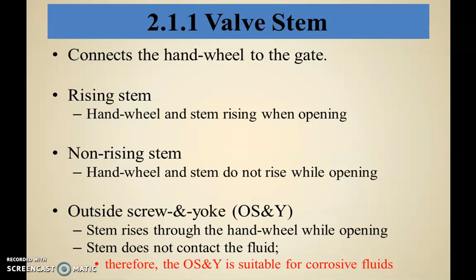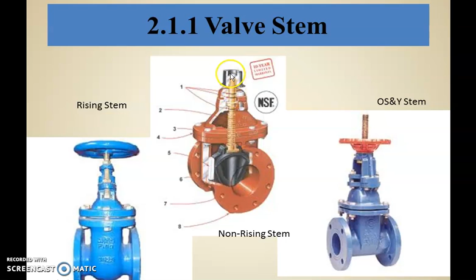In the rising stem or non-rising stem, the stem gets damaged by corrosive fluid, but in the outside screw and yoke valve, it does not get damaged. These are the valve stems. Here is the rising stem. When you rotate this one, it will move in the upward direction. This is the non-rising stem, moving in one place only. Here we will not see any rising, and this is an OS and YS type of stem.